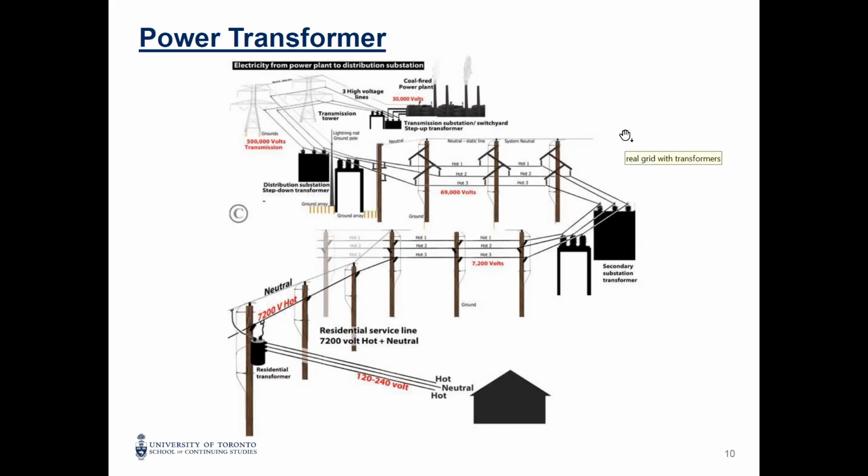We have the history. Yes, we have a question. Yes, please. Can a substation receive 2 supplies from different power stations? Yes, definitely. And not just one transformer. Well, definitely. So each transformer that steps down the voltage would have its own grounding system or network associated with it, or would they share the grounded network? They can definitely share the ground.